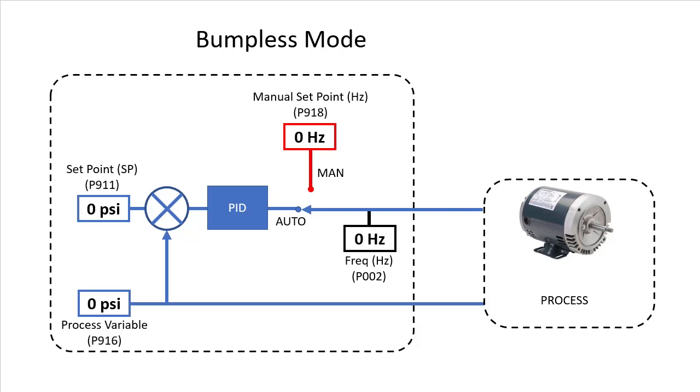So when PID starts, it sees the process variable and the set point are the same and it just goes about the business of maintaining that motor speed. The operator can then safely increase the set point to the desired level.